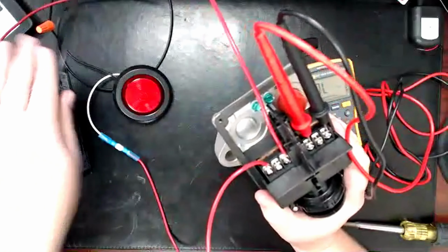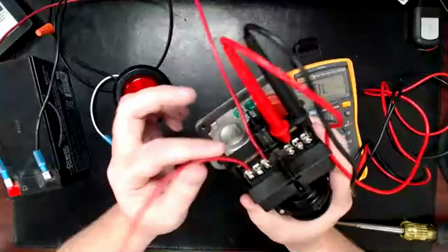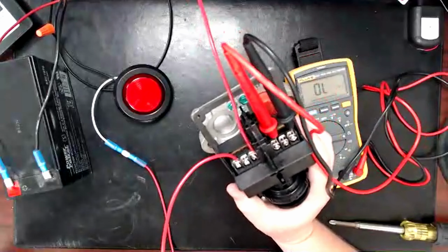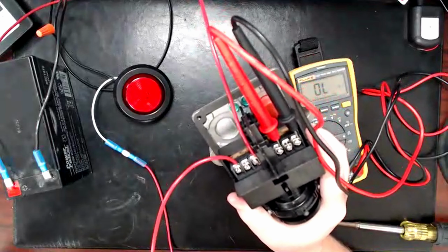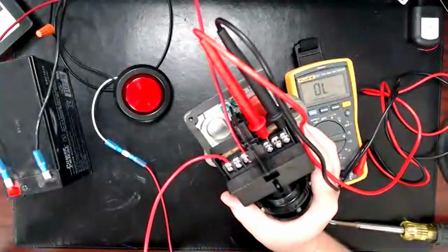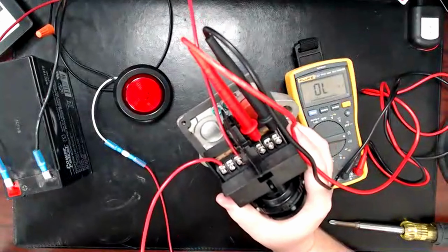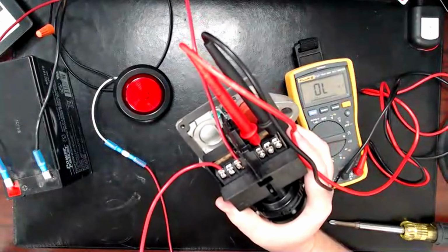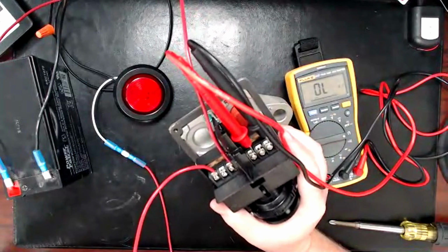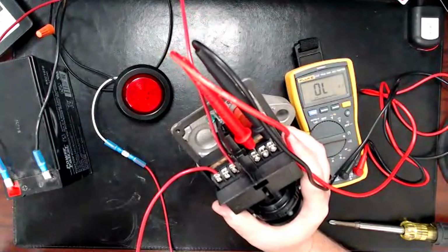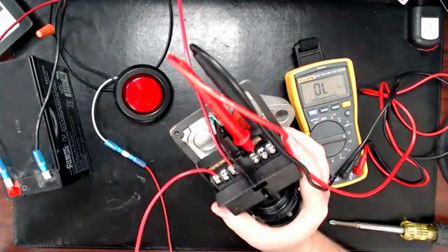So you remember the negative side went straight to the light. And then because we want the bell to normally not ring, we use normally open. Last week, we talked about air conditioner HVAC shutdown. We said we want air conditioners to always be turned on. So you use normally closed because the closed circuit is the turned on circuit. So in things like air conditioner and elevator recall, they want normally closed because they want those systems normally functioning, so normally turned on. And then whenever we go into alarm, we're actually overriding it and turning it off. So that normally closed terminal then opens up and it turns it off.